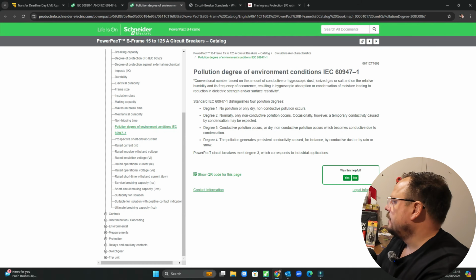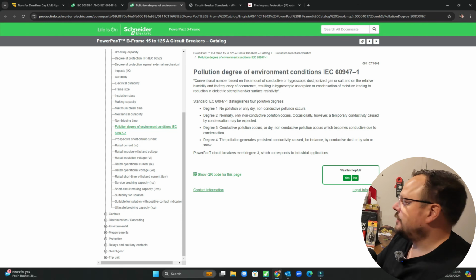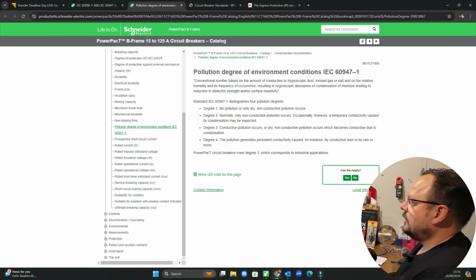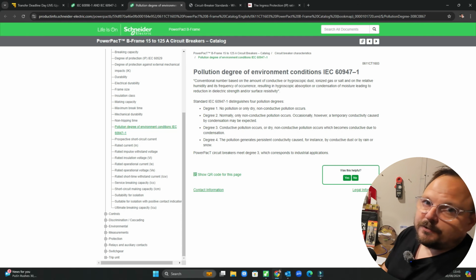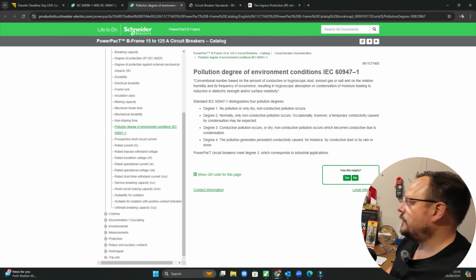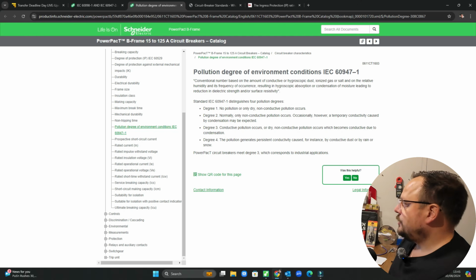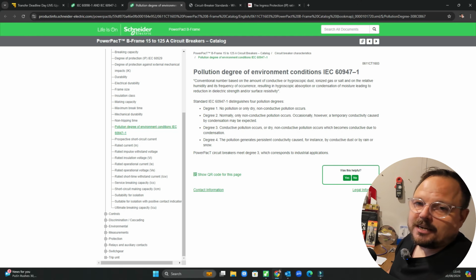and they are pages and pages thick in way more detail than just this little niche topic that we're talking about today. So this is one that actually explains what the pollution degree environments are, and they're set out in 60947-1, which, as we said at the start of this video, is the standard for your overcurrent protective devices. And it distinguishes 4 pollution degrees. So degree 1 is no pollution, or only dry non-conductive pollution occurs. Degree 2 is normally only non-conductive pollution occurs. Occasionally, however, a temporary conductivity caused by condensation may be expected. So that's if it's inside a dwelling.